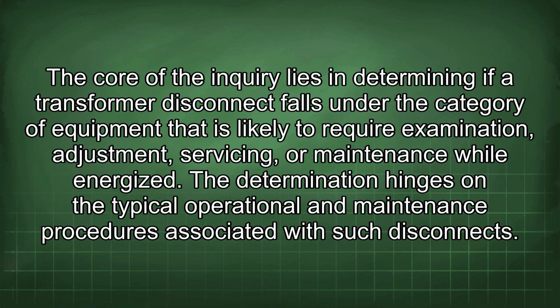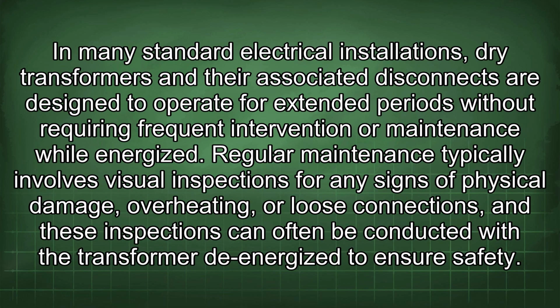The core of the inquiry lies in determining if a transformer disconnect falls under the category of equipment that is likely to require examination, adjustment, servicing, or maintenance while energized. The determination hinges on the typical operational and maintenance procedures associated with such disconnects. In many standard electrical installations, dry transformers and their associated disconnects are designed to operate for extended periods without requiring frequent intervention or maintenance while energized.